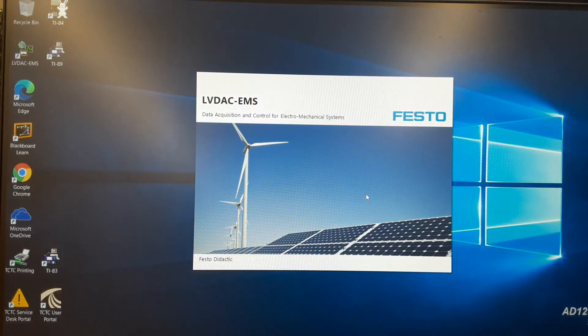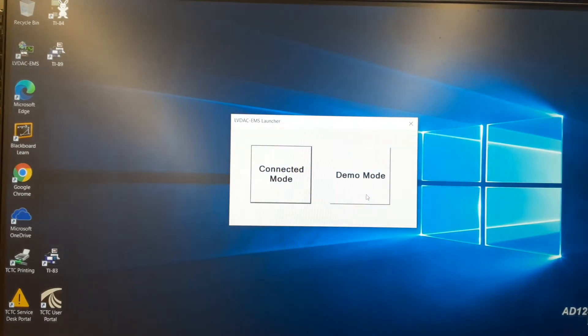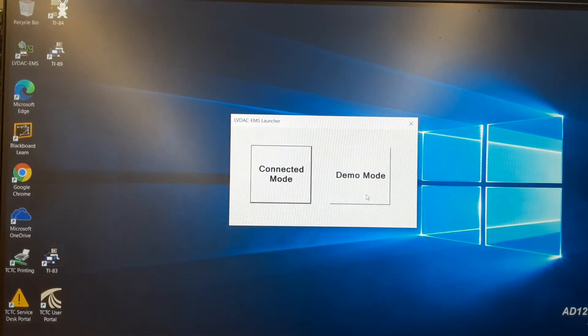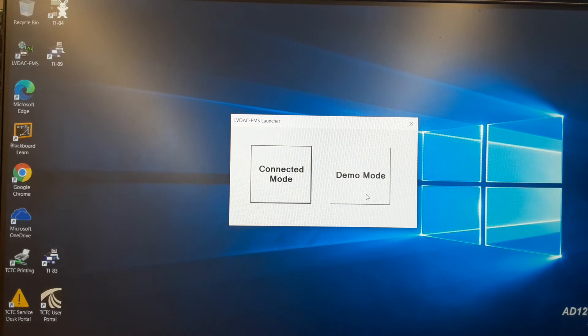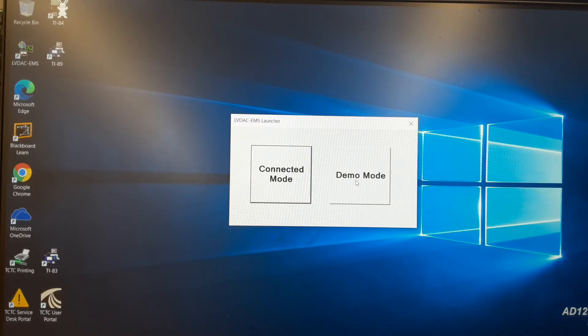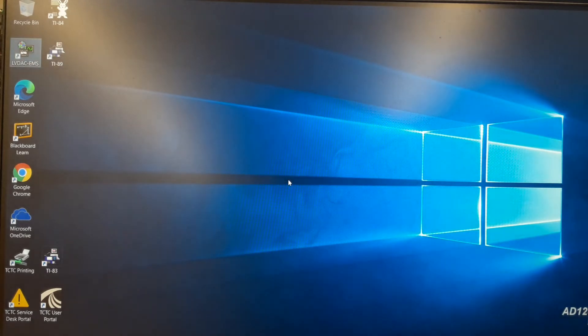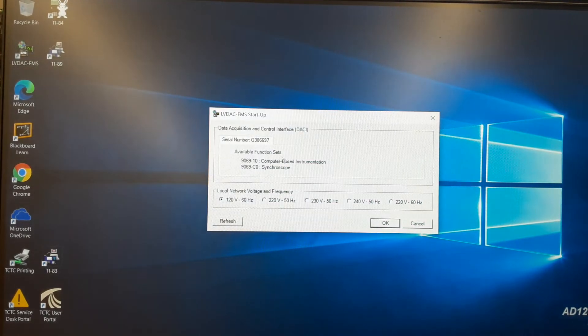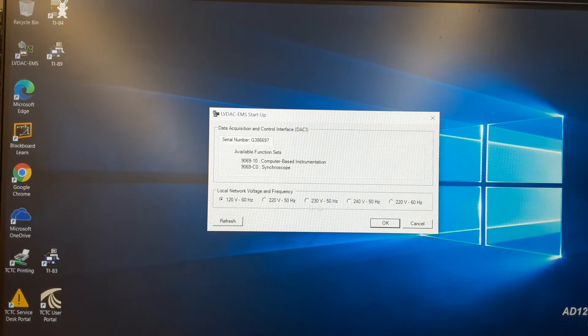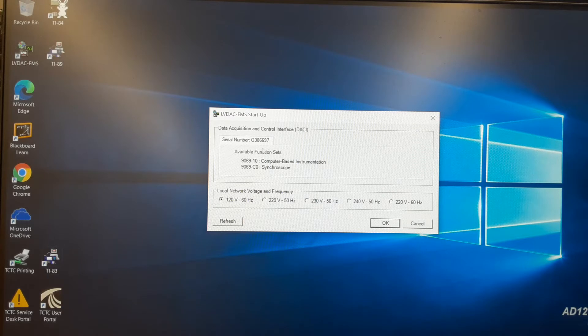So make sure, before starting this software, that you do have your USB cable connected to the acquisition module and also your 24 volts connected to the module first. It just makes it easier to do this setup. So once you get to this window, you're just going to hit Connect Mode. And then if you have power and your USB connected, it should find the module. And you should see this screen here.